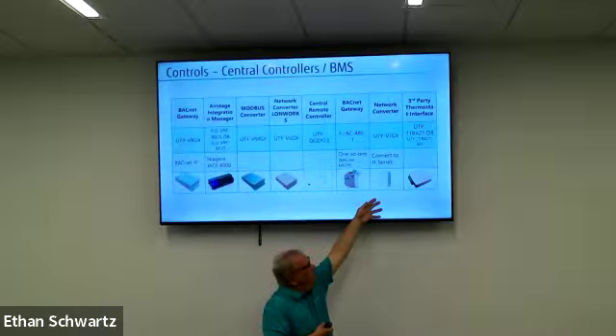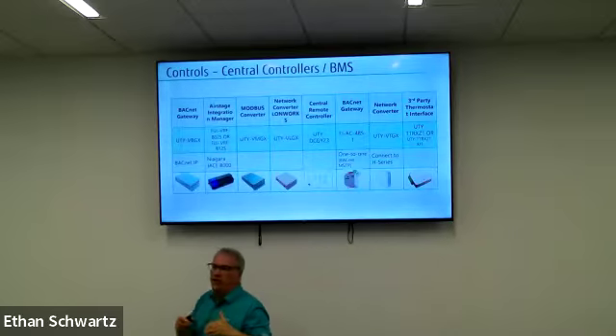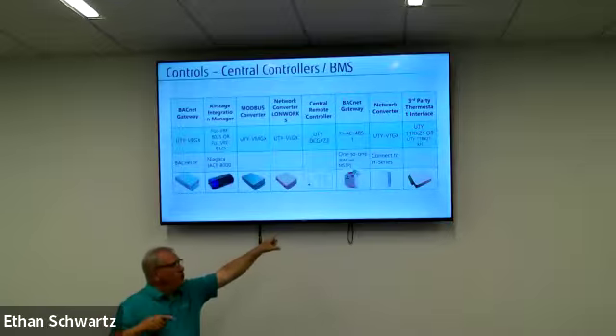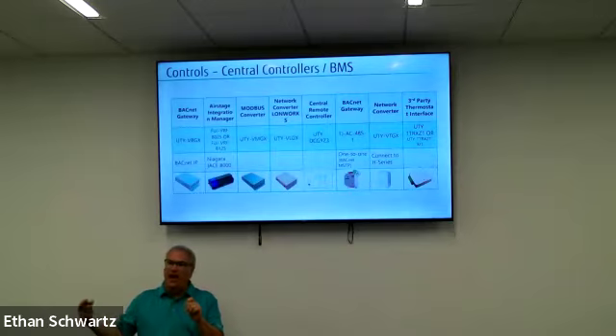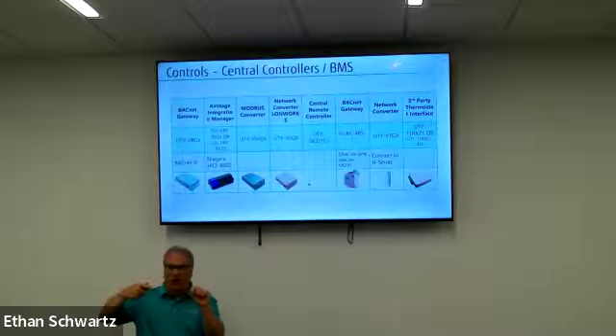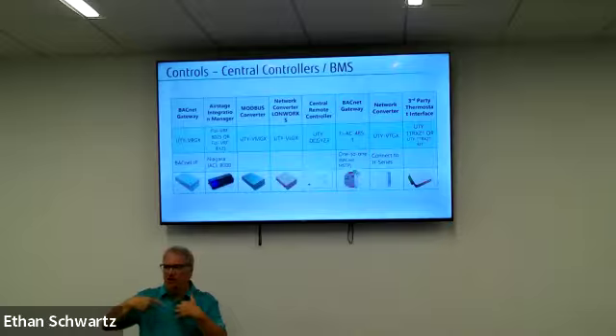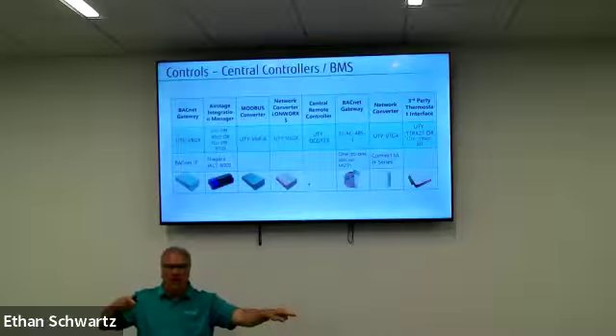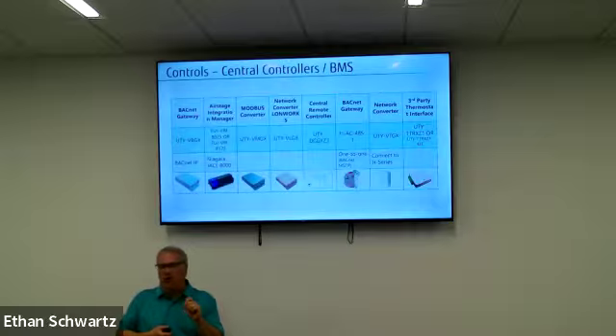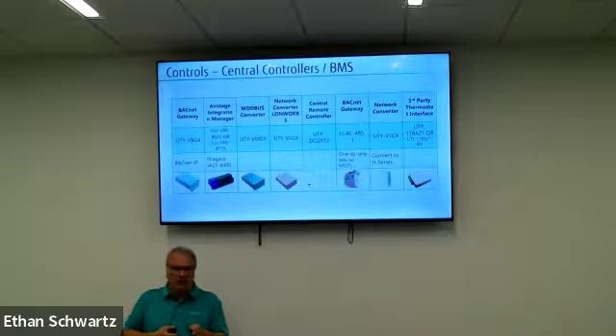On this side it takes the R and G and Y1, Y2, W1, W2, if it's wired that way, and then turns those into signals, because we're going to set dip switches in there so that a call in on Y1 means this level of cooling call in Fujitsu language to our indoor unit. When it does that, you lose some of the inverter compressor speed variability, and it works best, in my opinion, if the thermostat that's feeding in is a two-stage heating, two-stage cooling.